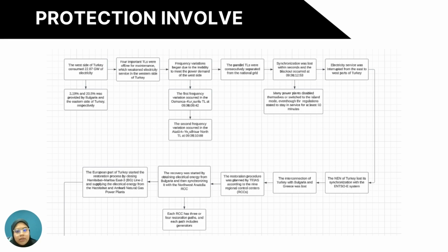Synchronization was lost within seconds as the breakup occurred at 9:36:12:53, which means that the west side of Turkey lost its connection to the European Network Transmission System Operator (ENTSO-E), the European electricity grid. This caused a blackout in the west of Turkey.